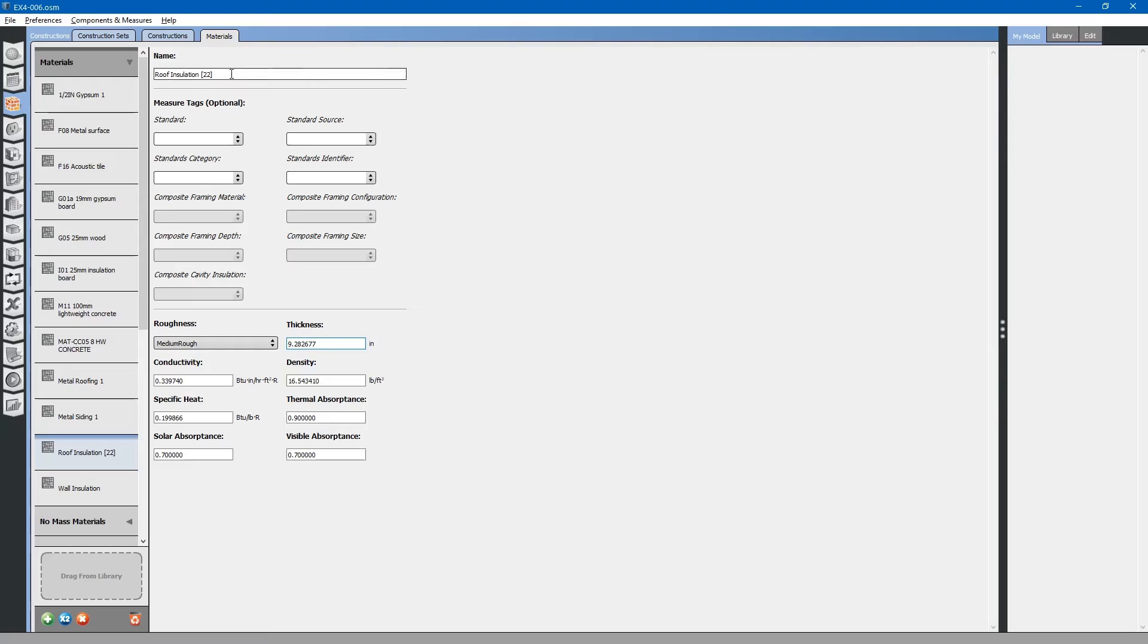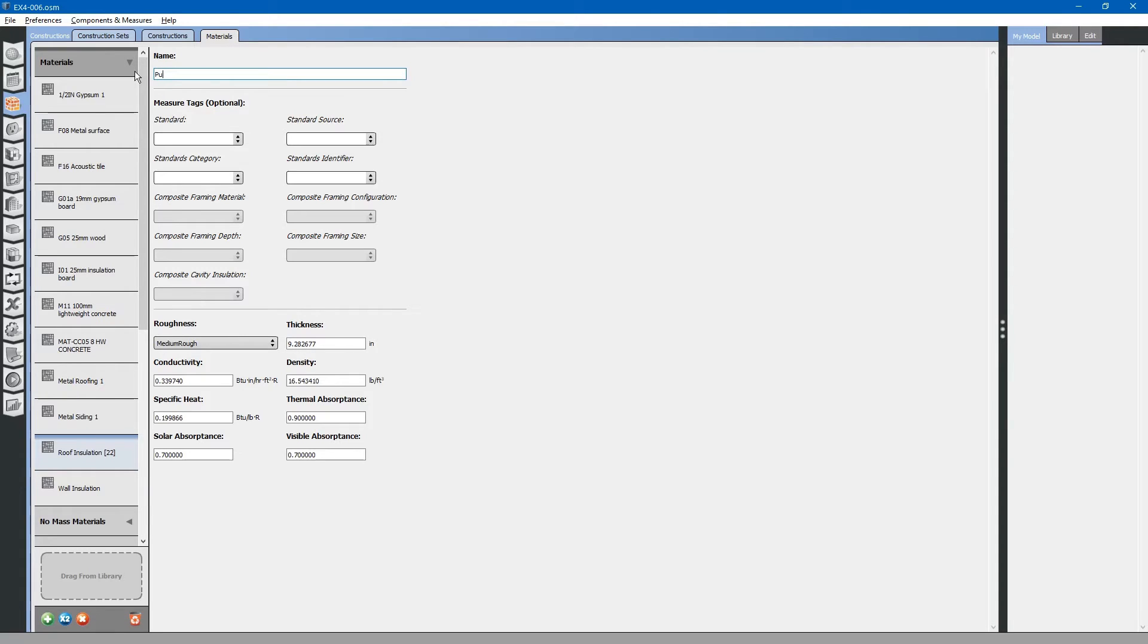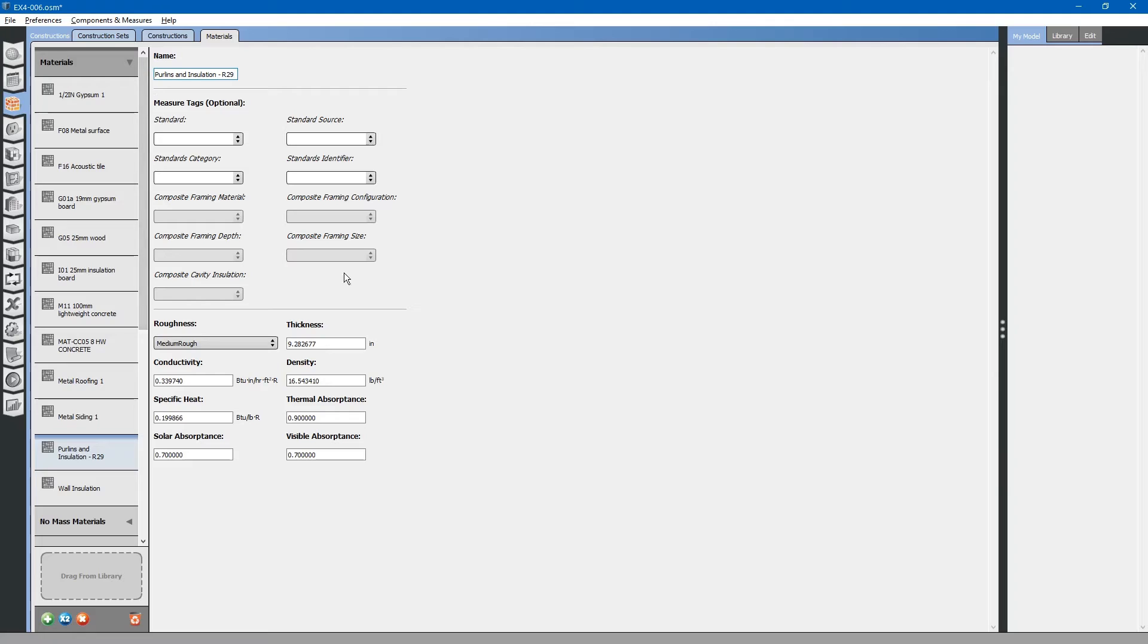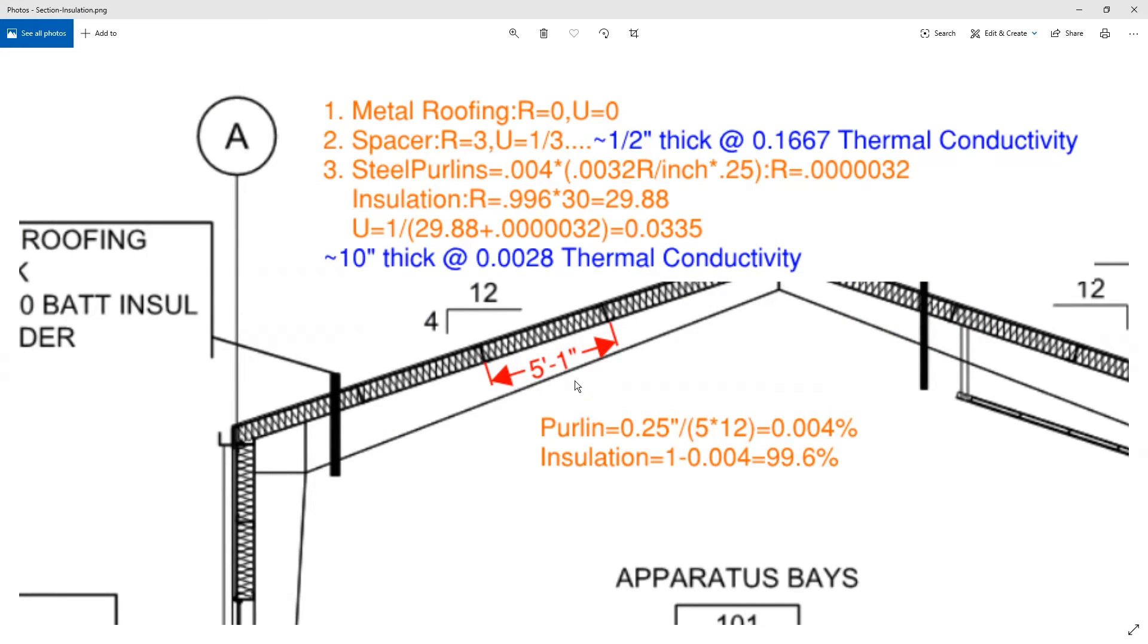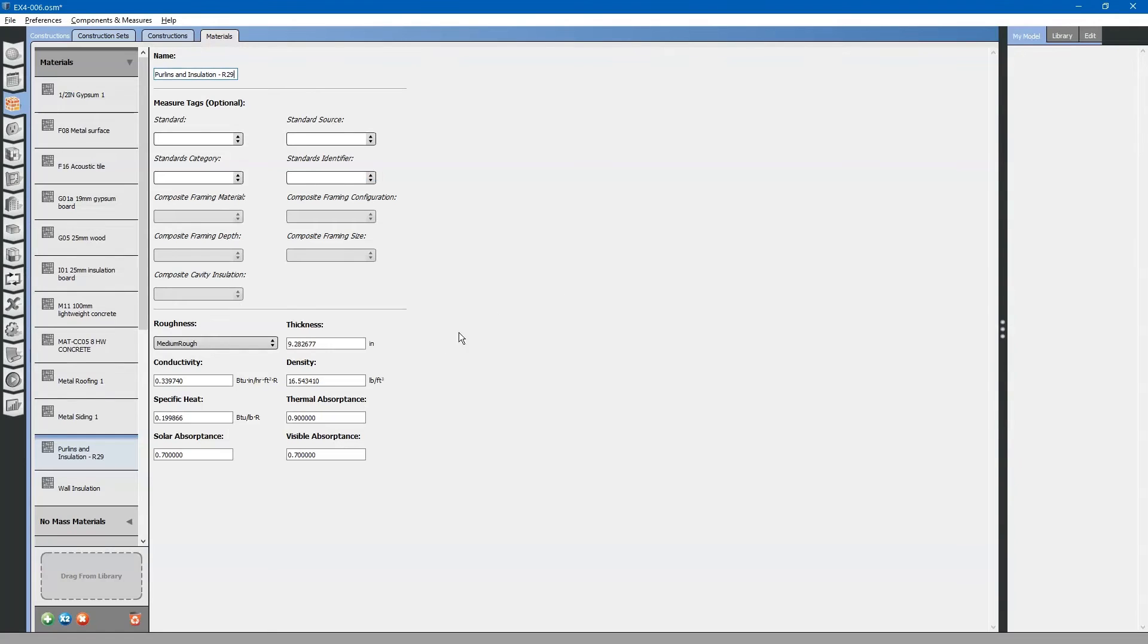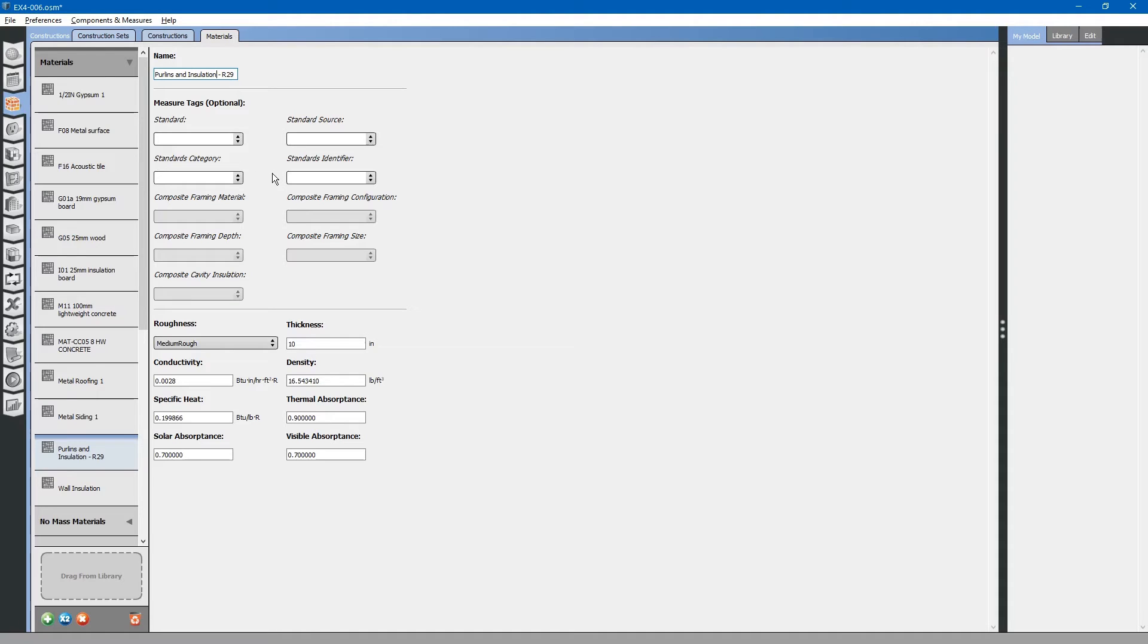What we will do is we are not going to be using this roof insulation for any other assembly. We will just rename this. Purlins and insulation R29. You will notice that the purlins plus insulation is approximately 10 inches thick. It has an R value of 29.88 which is a 0.0028 thermal conductivity.